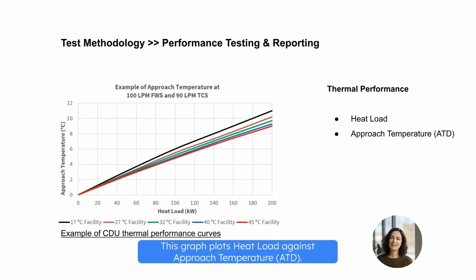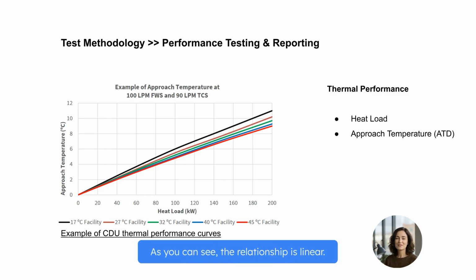This graph plots heat load against approach temperature, ATD. Remember the formula: ATD equals TCS supply minus FWS supply. As you can see, the relationship is linear. Engineers, pay attention to the colored lines. Different facility water temperatures result in slightly different performance curves due to fluid property changes. You need to select the curve that matches your facility's specific operating point.